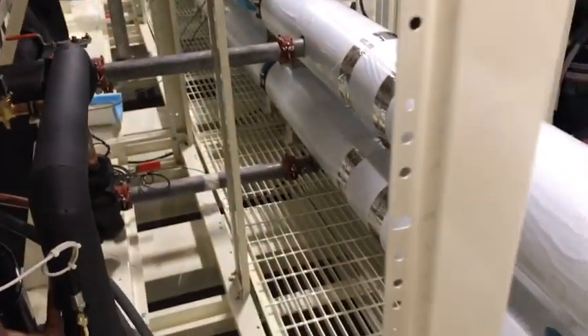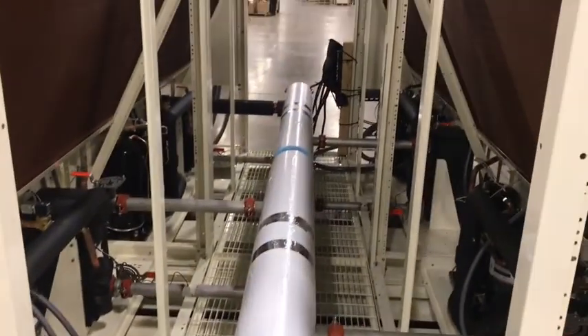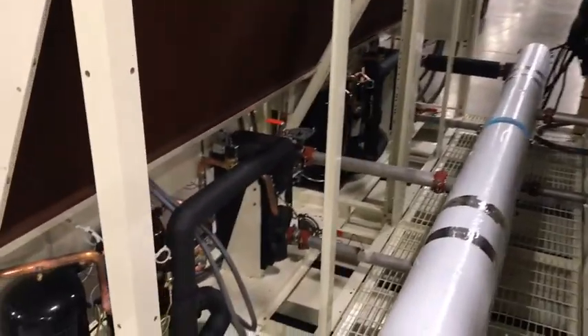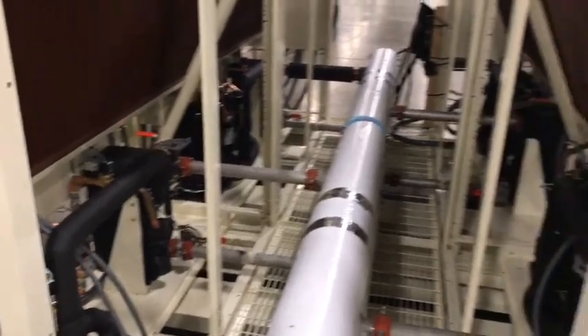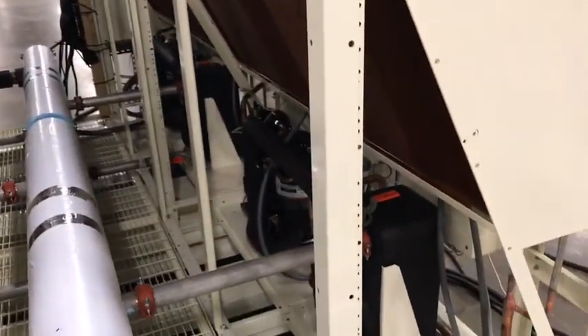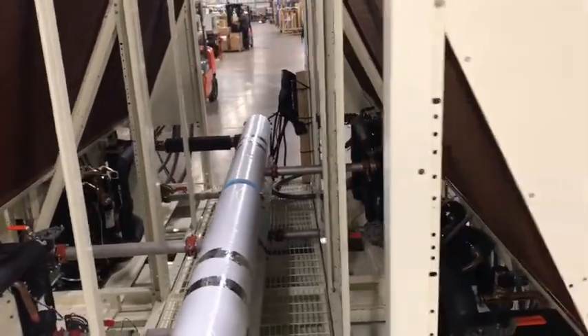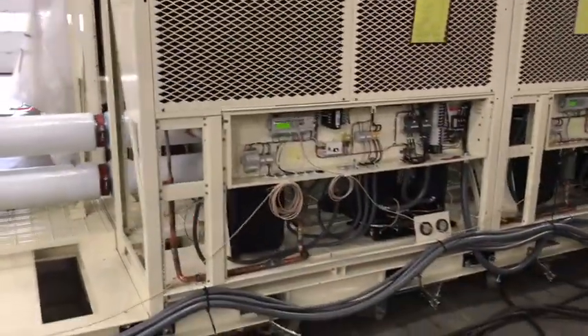The lowest header is the leaving connection for the mechanical modules. That's chilled water that has come out of the evaporators in the mechanical modules. And then that lowest header also serves to carry the water back through the opposite end down where the free cooling module is, so that we can have supply and return from the same spot of this array.